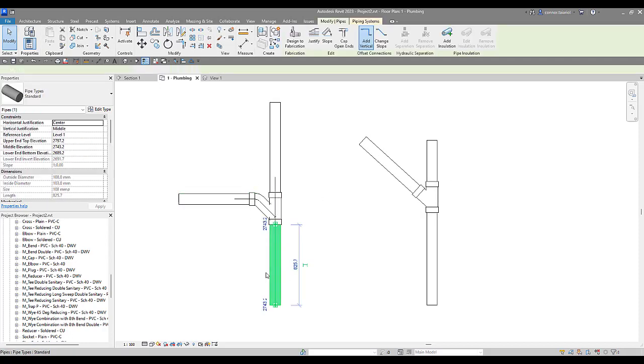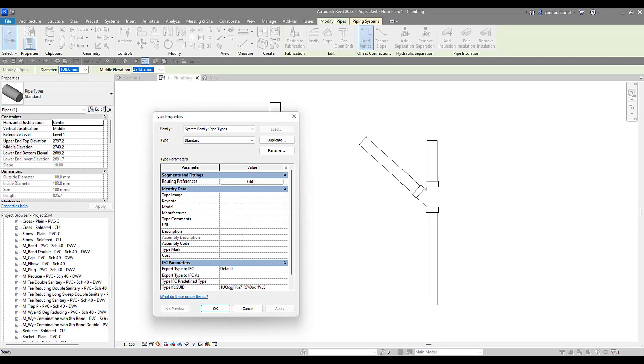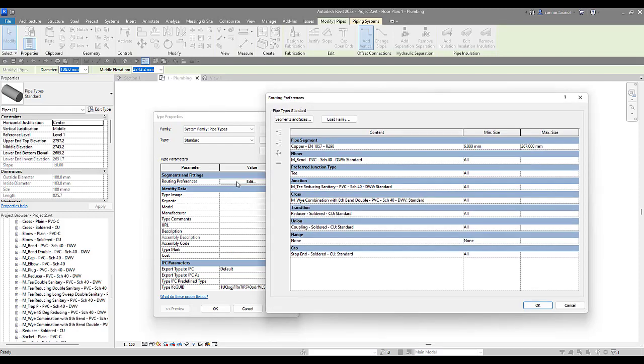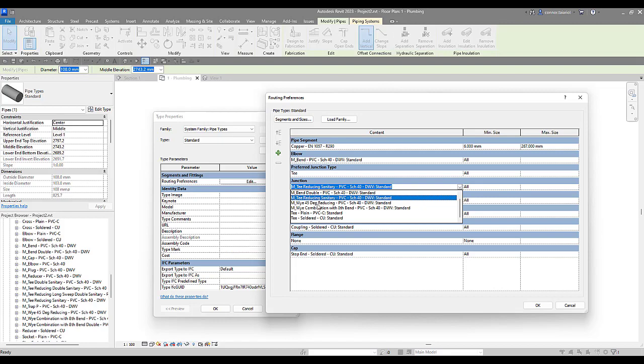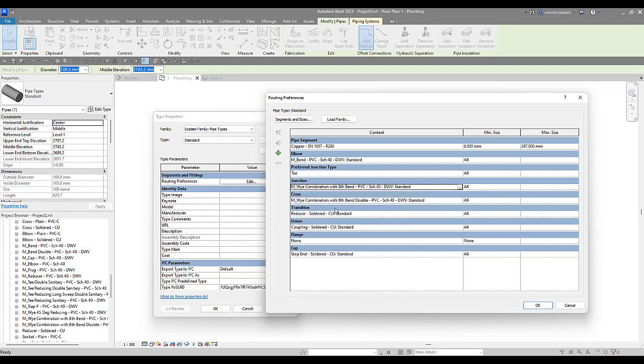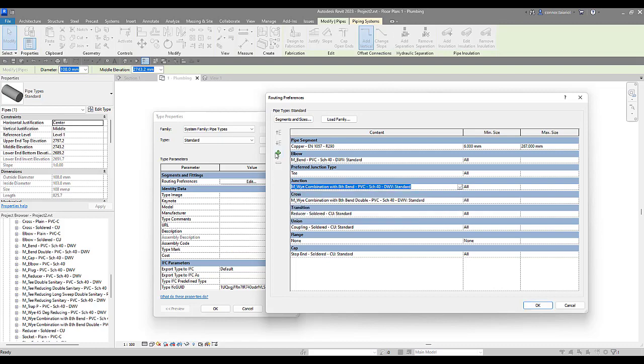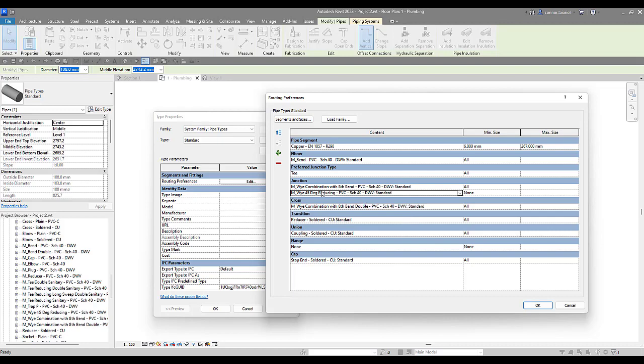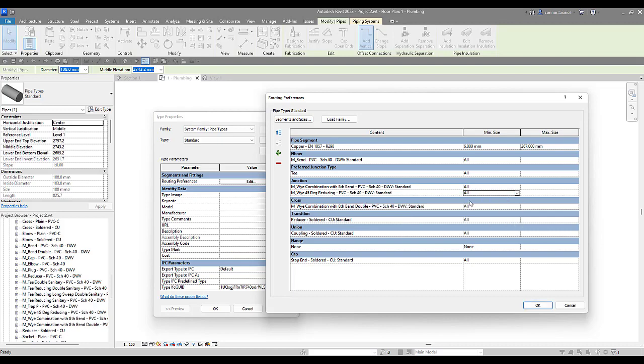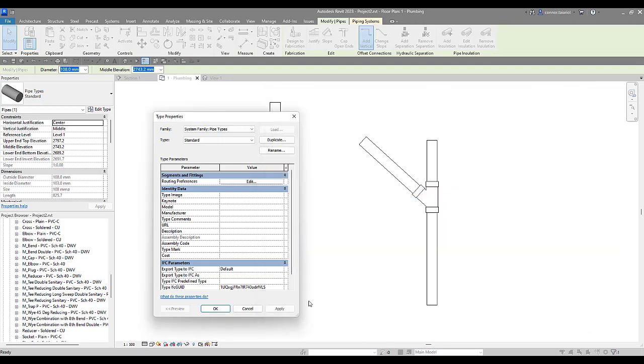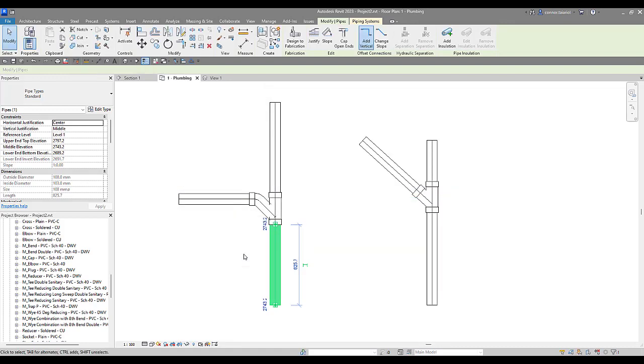We're going to select on our pipe actually. And we're going to go to edit type. Routing preferences is where we can set what fittings go in automatically. So come in here we're going to go to edit. And we can see we've got a sanitary reducing T here under the junction. So we're going to change that to our combination eighth bend. And we're also going to add the reducing 45 degree reducing Y as well. Change the min size to all for both of them. And then press OK.